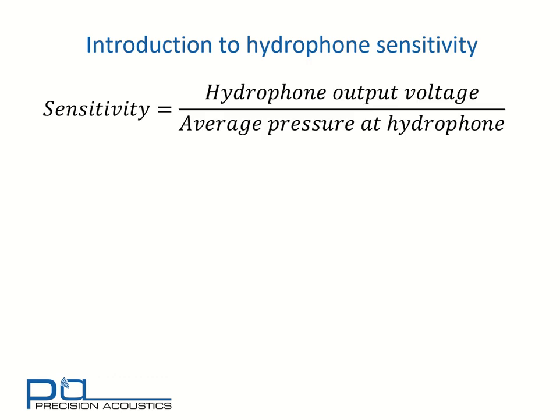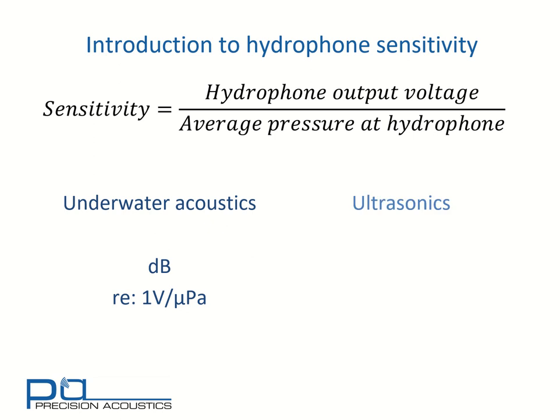Sensitivity is simply the hydrophone's output voltage divided by the average pressure at the hydrophone active element. In underwater acoustics, it's common to use logarithmic units, in which case decibels relative to 1 volt per micropascal are commonly used. In ultrasonics, linear units are more commonly used, in which case we consider millivolts per megapascal or nanovolts per pascal appropriate for representing sensitivity.